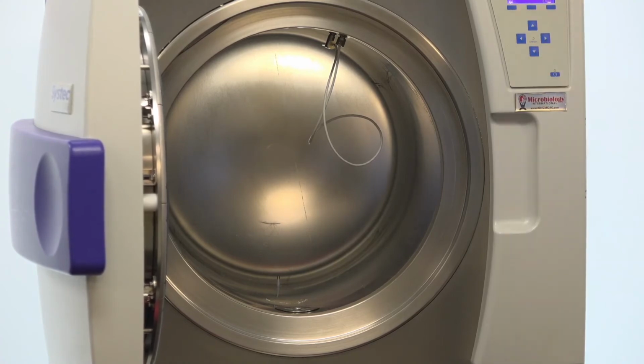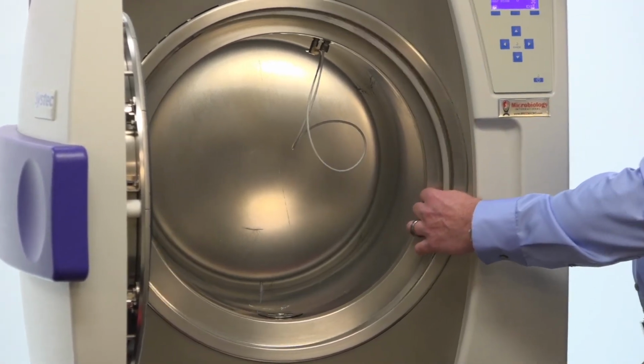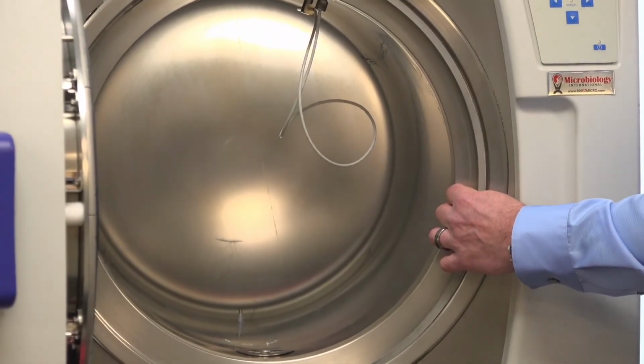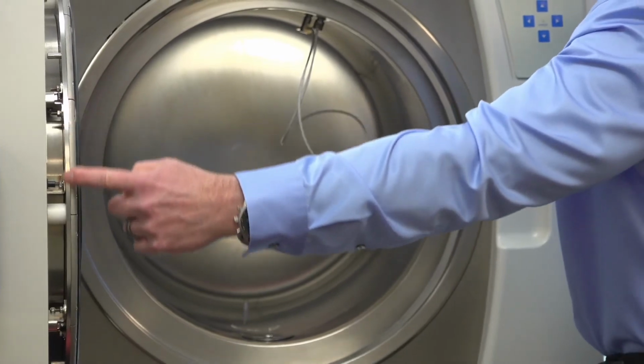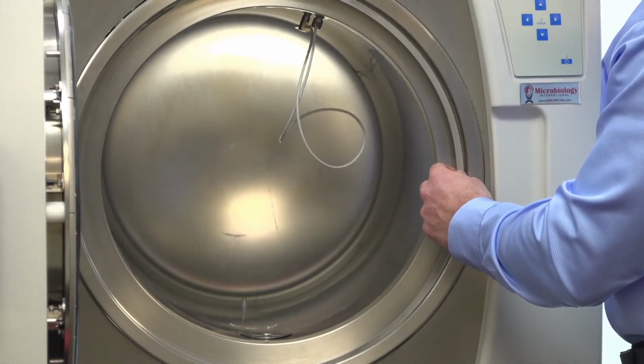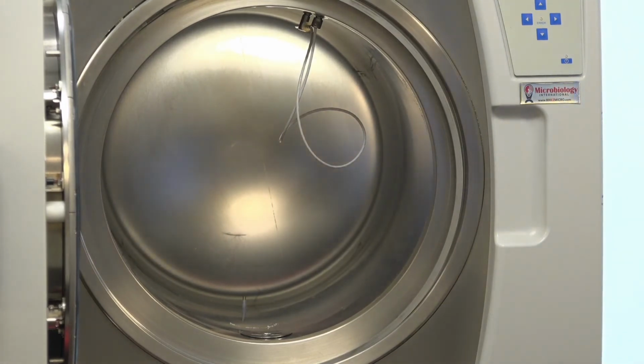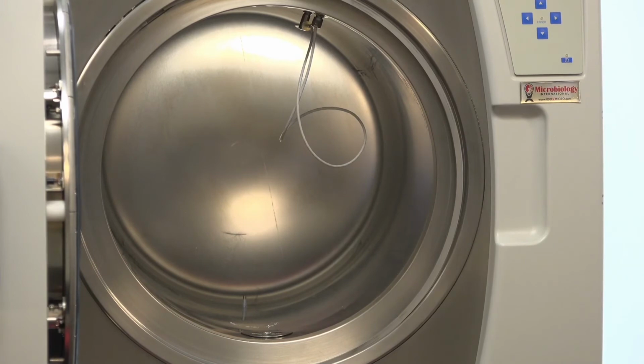The way the door ring works, that is the locking ring that you see that has just come out here. It would seal directly around the outside of the door, so it's going to seal around this door here and lock it into position. This ring has to have power in order to open. In its steady state, which is with no power, it is closed. So losing power is not going to affect opening and closing. You have to have power in order to open the door. The amount of pressure that this requires is roughly 8 kPa, which is less than 2 psi. That is the maximum amount of pressure that can be inside of the instrument at any given point that will allow that ring to open.